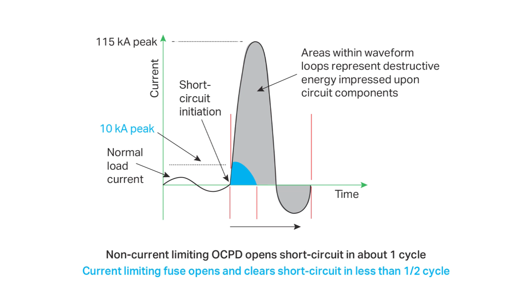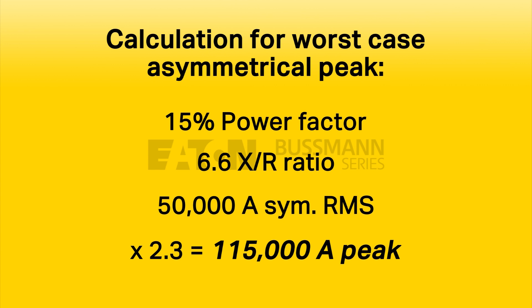The asymmetry or magnitude of the first peak is a function of the X/R ratio, or total resistance and reactance in the system. To calculate the worst case asymmetrical peak, assuming 50,000 amps RMS symmetrical available at a 15% power factor, or X/R ratio of 6.6, 50,000 amps would be multiplied by 2.3 to equal approximately 115,000 amps asymmetrical peak.